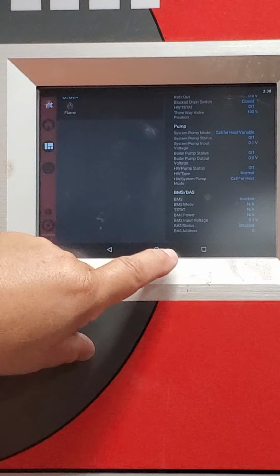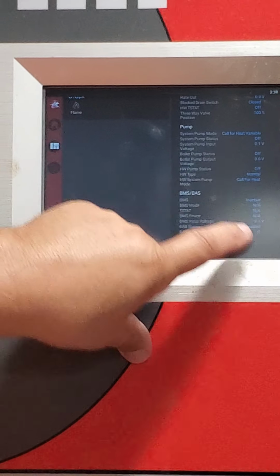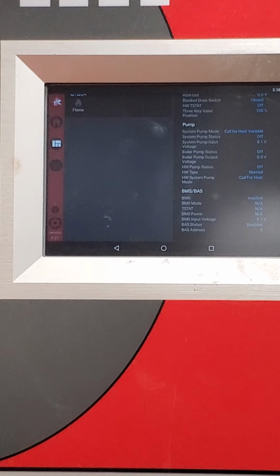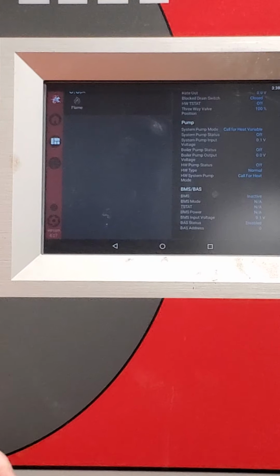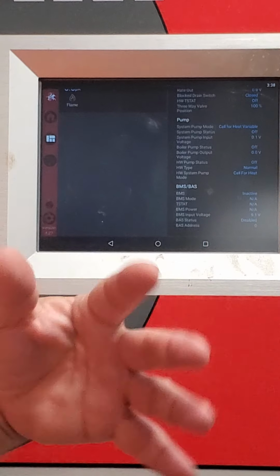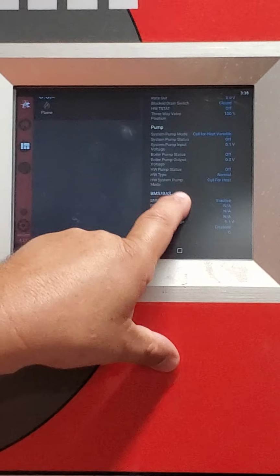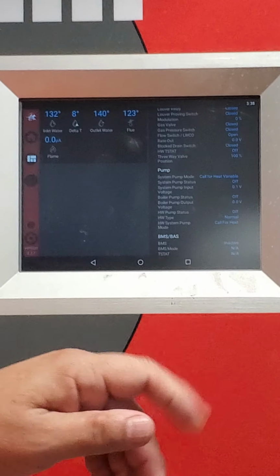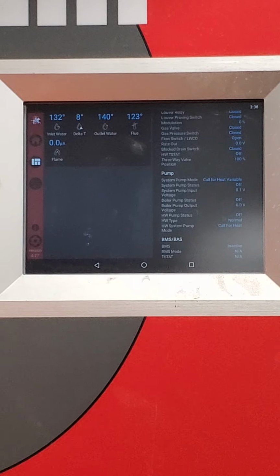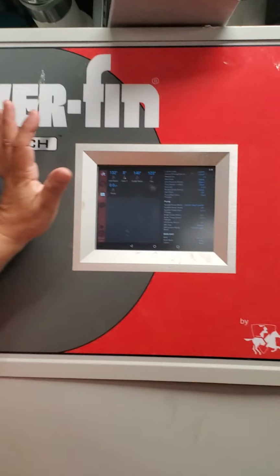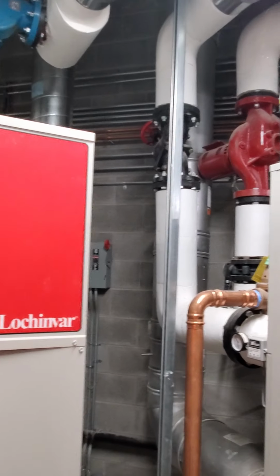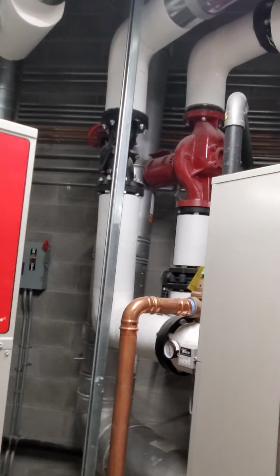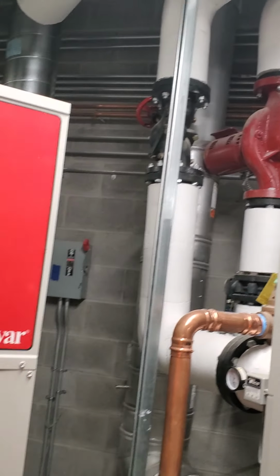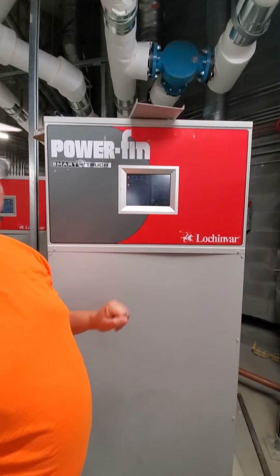Take that screen and you can scroll it up. You've got your BMS, BAS inputs. You can see if the building automation system is sending any information to it, or a 0-10 signal. You can read the actual signal coming into the boiler. You can see if your pumps are running. There is a boiler pump for each boiler. That pump must run for this boiler to run. So if the boiler's locking out on flow switch or low water cutoff, there's a good chance it's the pump.